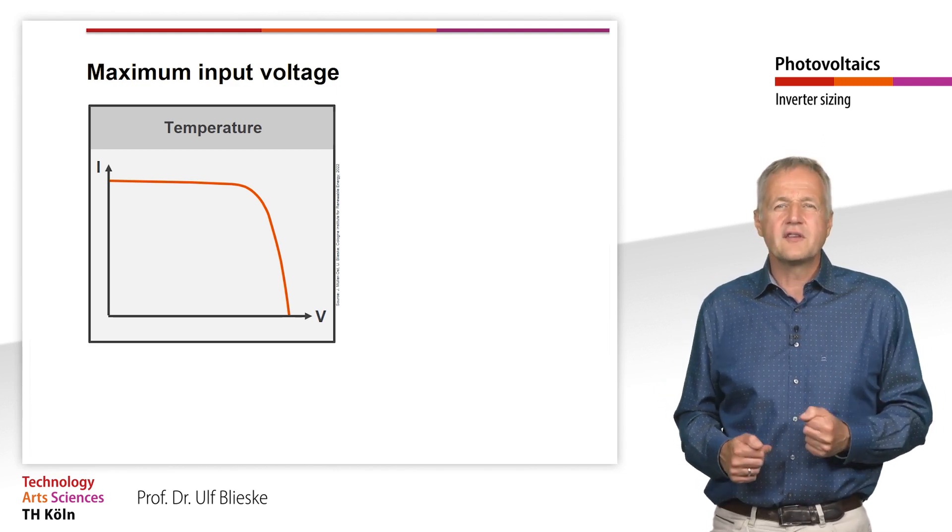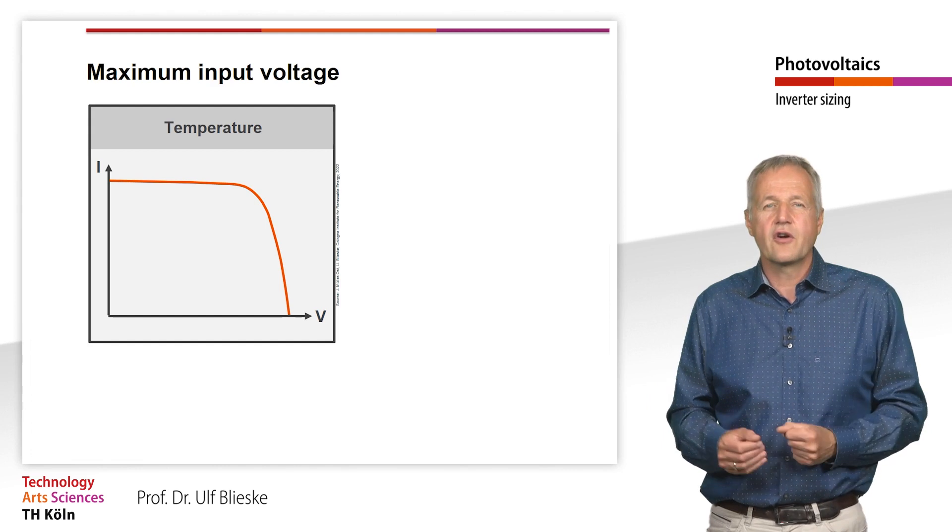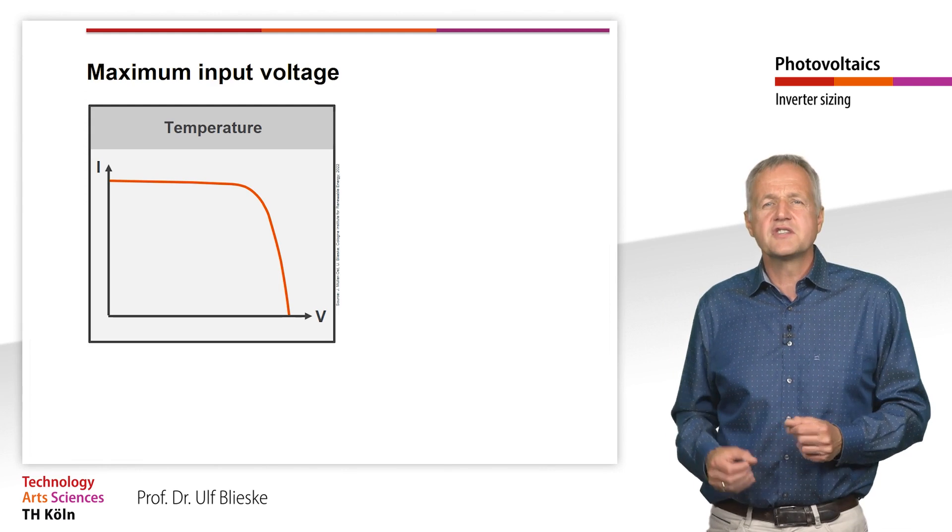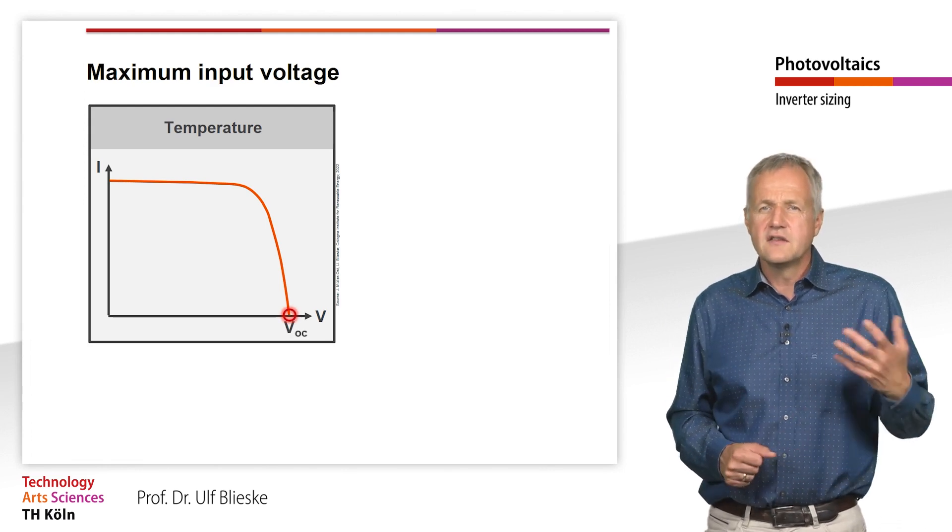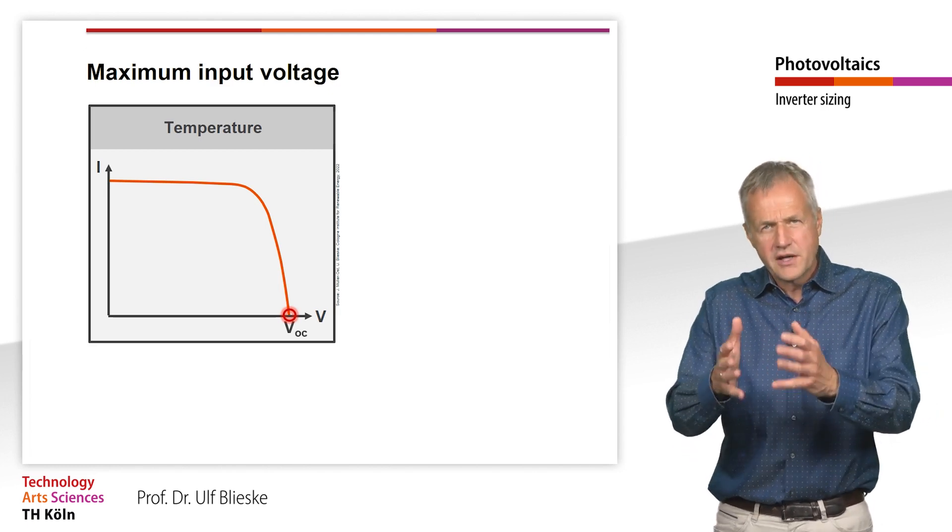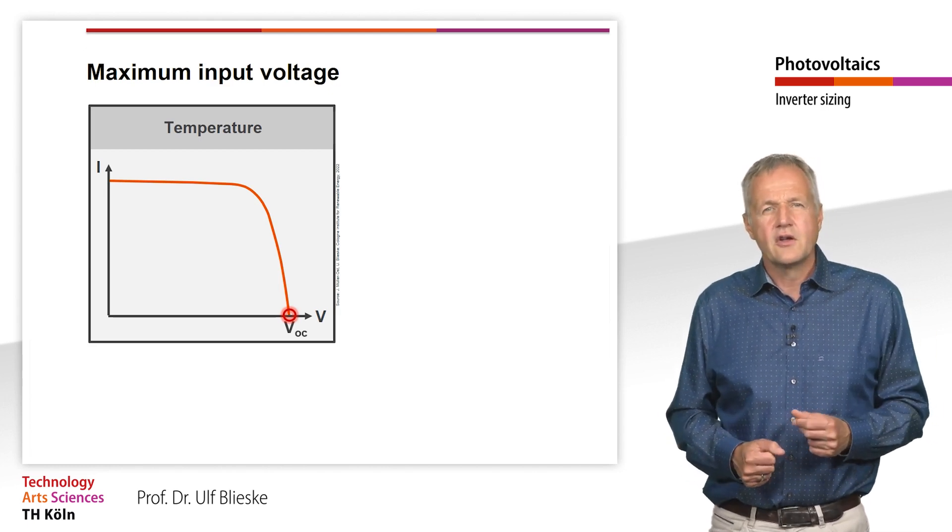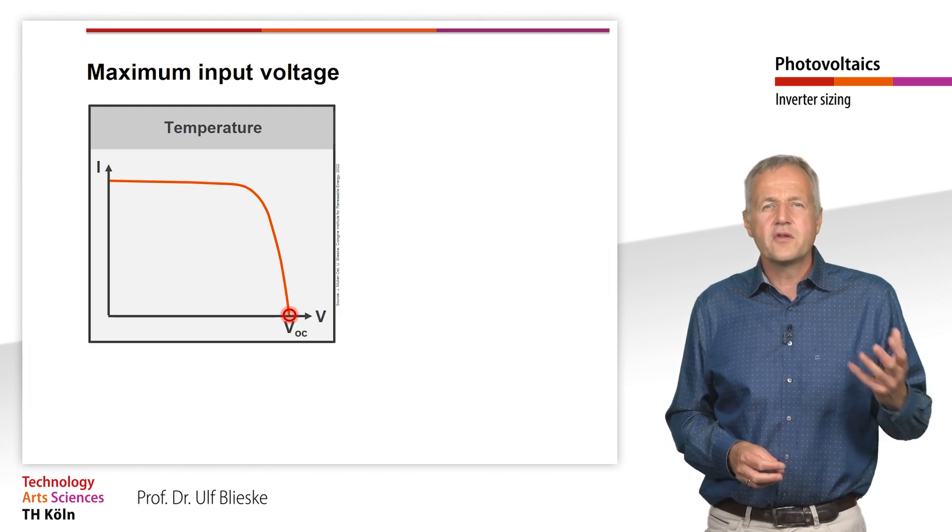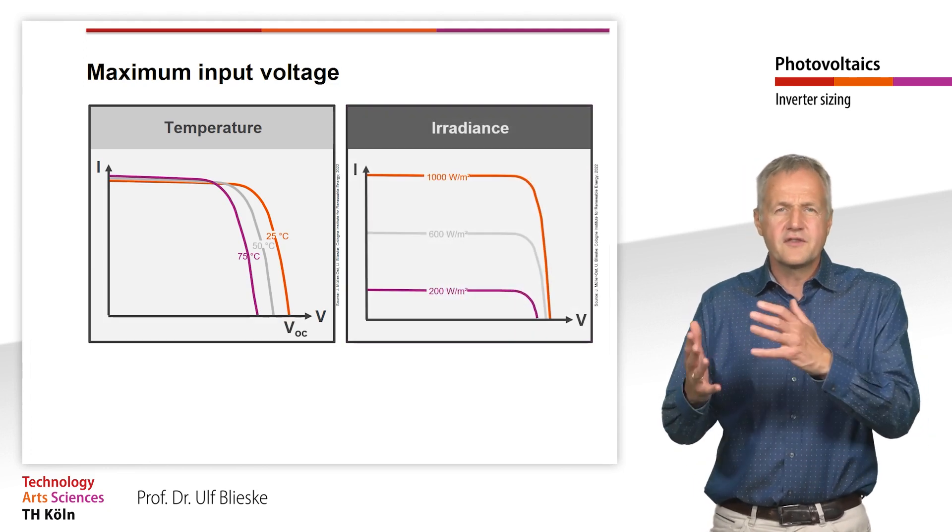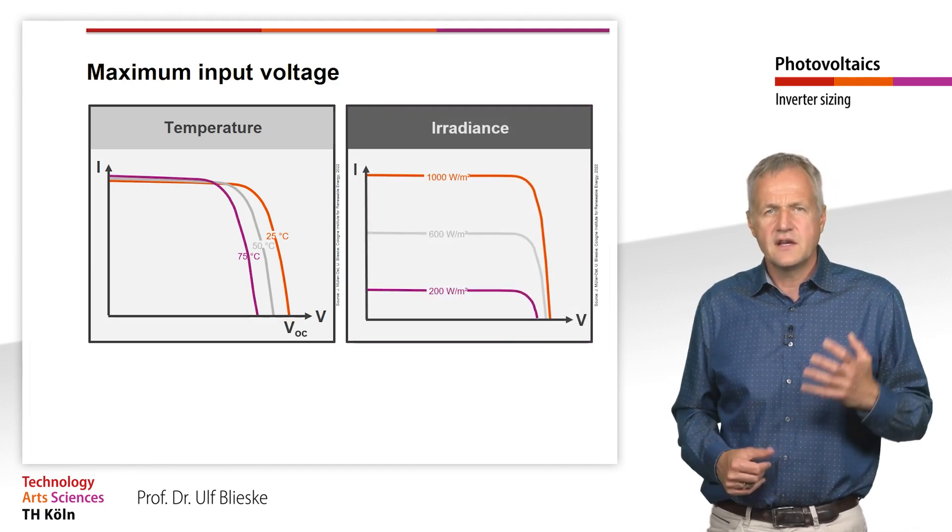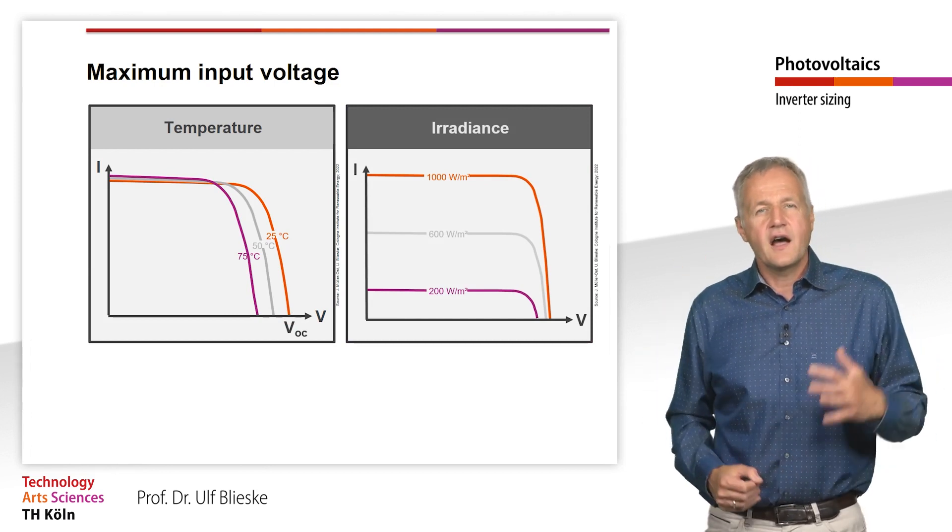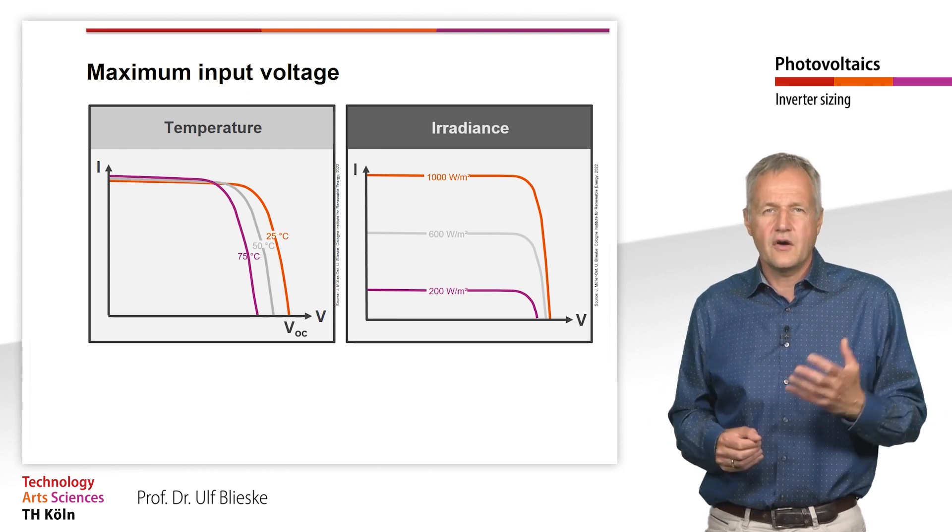For this purpose, let us once again visualize the characteristic curve of a solar module. The highest possible voltage is the open circuit voltage. This voltage is present for example when the inverter cannot feed into the public grid due to a power failure. We have also learned that the open circuit voltage is not constant but changes with both the cell temperature and the irradiance. In general, the lower the cell temperature and the higher the irradiance, the higher the open circuit voltage of the solar generator.